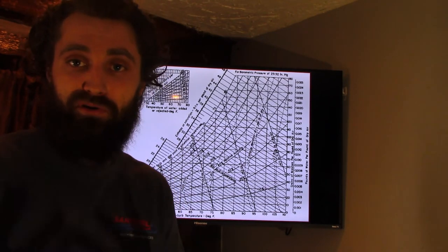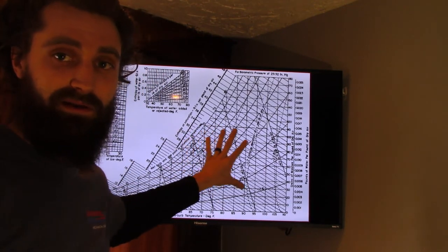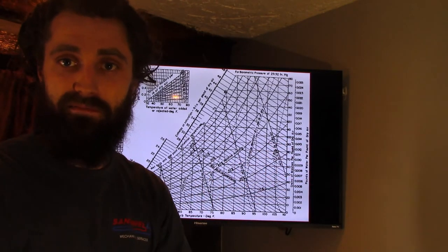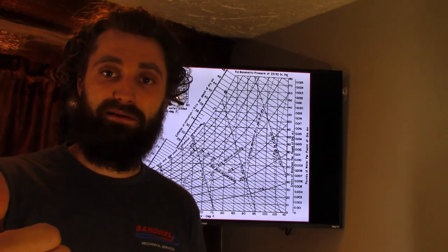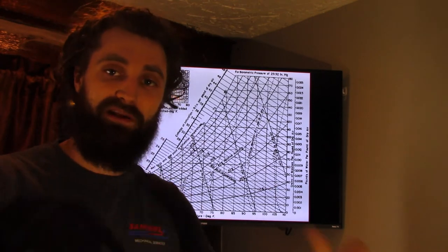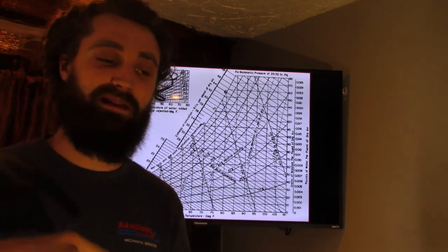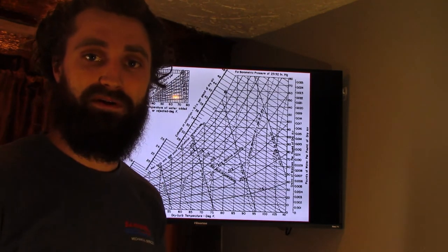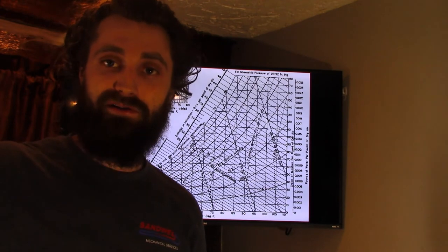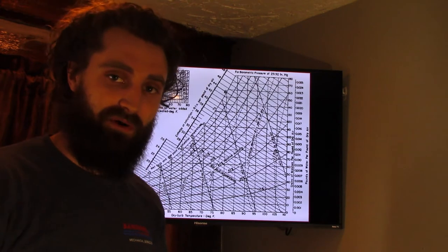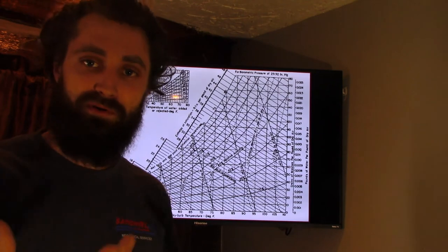Or it may say that, hey, the amperage is really high. It may be producing good output on the air side. It may be giving you that 37,000 BTU. The amperage may be way out of whack, okay? If you've got an ECM blower and it's running full tilt up in the attic to give you that 1,300 CFM or that 1,289 CFM, but that ECM blower is just really wound up to do it, you'll see a really high amperage rating. You'll see a high wattage of your ECM blower. You'll put that into the formula and you'll say, wow, this 16 SEER system is only running at 13.1 SEER. What's the deal with that?